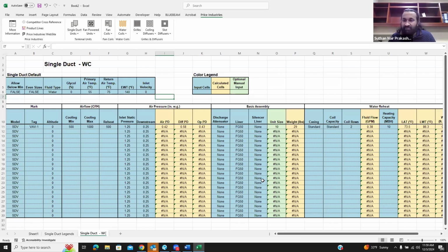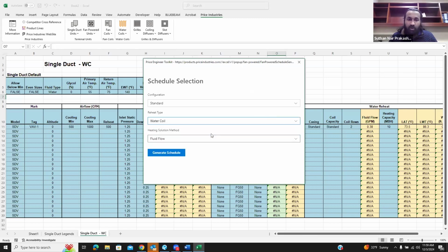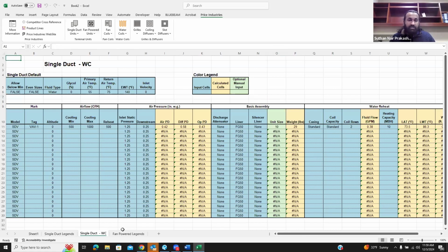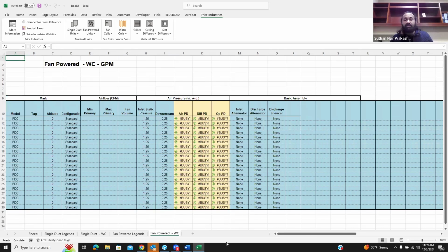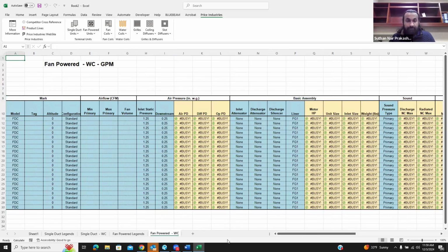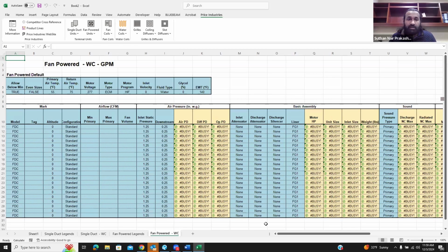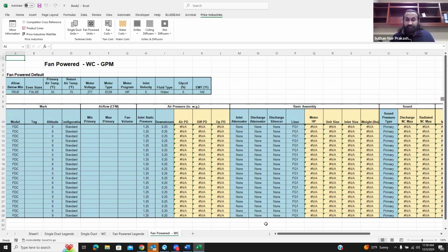If you have fan powered terminal boxes or fan coils as well in a particular job, you don't have to save this and create a new Excel sheet or something. You can just go here and create a fan powered schedule, and give standard, reheat type as water. I'll calculate with fluid flow and generate schedule. It's going to create a new sheet here for me with the fan powered data that I need to input here.